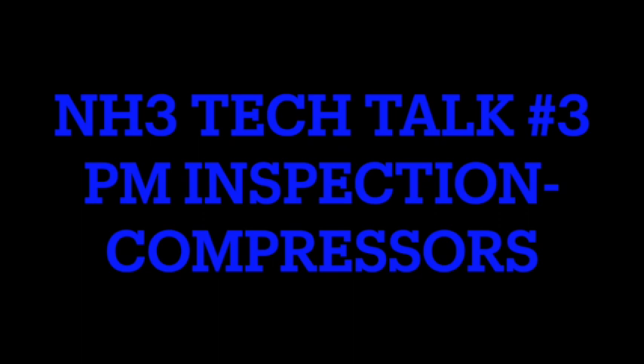Most panels will have like a freeze frame. If it's not like an old school panel, usually your Quantum LXs and above, as far as Frick's concerned, will have like a freeze screen for when the compressor shuts down. Check out the freeze screen. Try to do detective work as to why you think they had an issue. It could have been a power outage and it's got a bunch of alarms on it, or a high level that'll show like auxiliary failure or stuff like that. But auxiliary failure could be something like a starting failure, with the soft start or a VFD, or I don't know. Kind of see what's up.